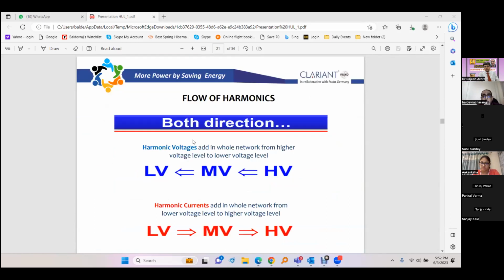We have voltage harmonics and we have current harmonics. Normally, all the non-linear loads generate current harmonics, and they flow from the load towards the bus upwards. From the load, they go to the LV bus, then to the MV bus, through the transformer to HV, and then back to the grid. And at every stage they get converted into voltage harmonics and voltage disturbance. And all this voltage distortion comes back from the grid, from high voltage to medium voltage to LV. So this is the flow of harmonics.